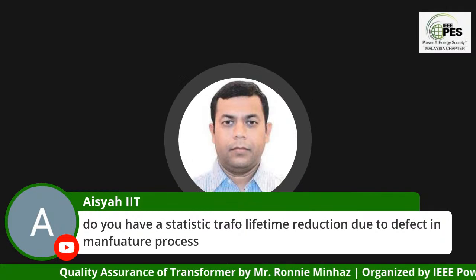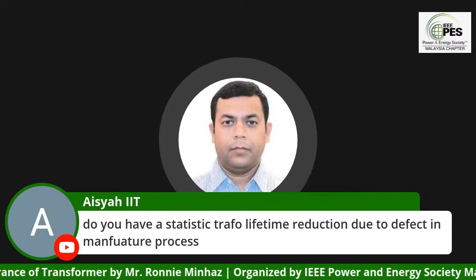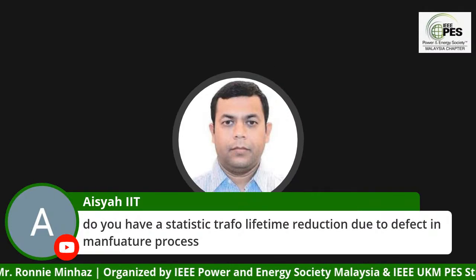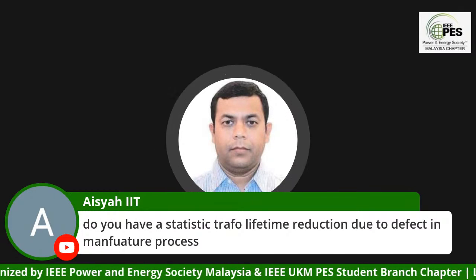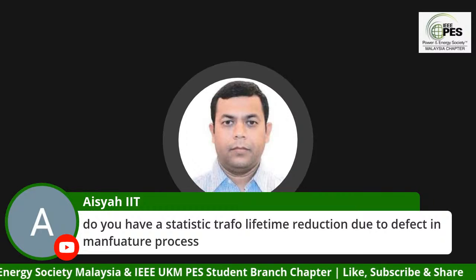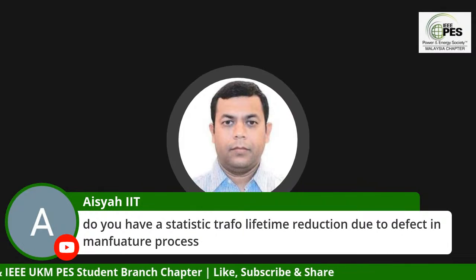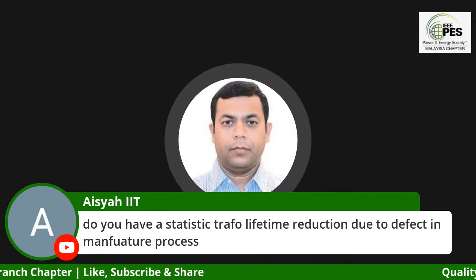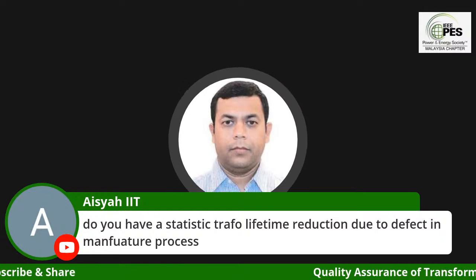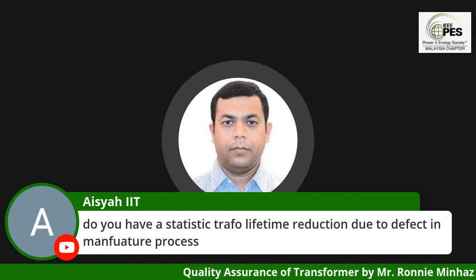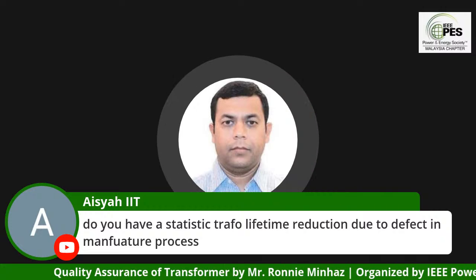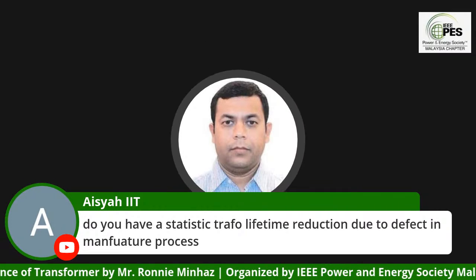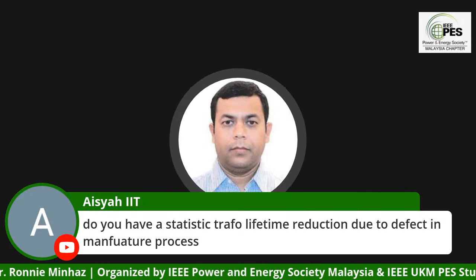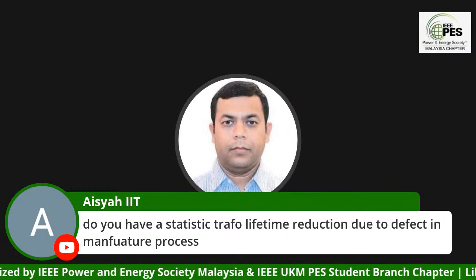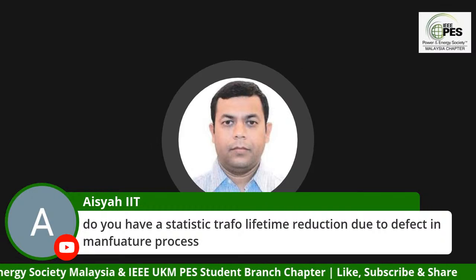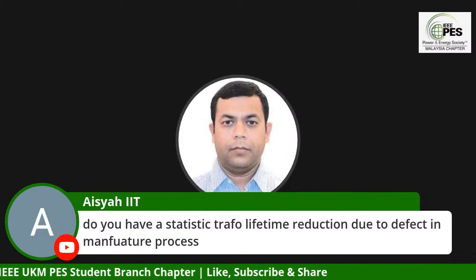So now, why will the life of the transformer be 7 years? What happens if the temperature inside the transformer goes above 120 degrees C? The IEEE standard says that if the transformer temperature goes above 120 degrees C, for every 8 degrees C, you lose the life of the transformer by 50%. Why by 50% is because of the carbon hydrogen chain, which we call polymerization. So decomposition of this chain happens, we call it depolymerization. So depolymerization increases.